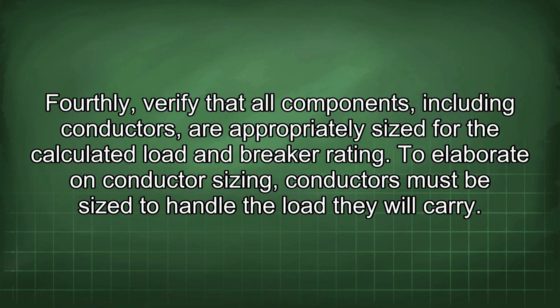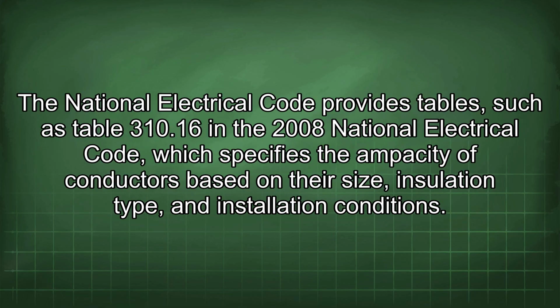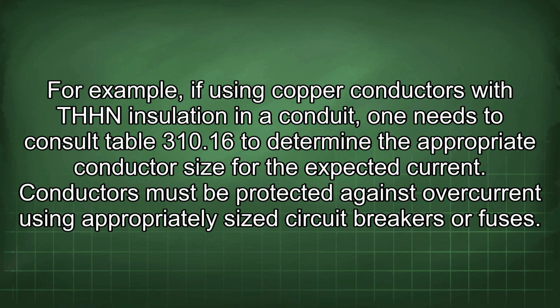To elaborate on conductor sizing, conductors must be sized to handle the load they will carry. The National Electrical Code provides tables such as Table 310.16 in the 2008 National Electrical Code, which specifies the ampacity of conductors based on their size, insulation type, and installation conditions. For example, if using copper conductors with THHN insulation in a conduit, one needs to consult Table 310.16 to determine the appropriate conductor size for the expected current.